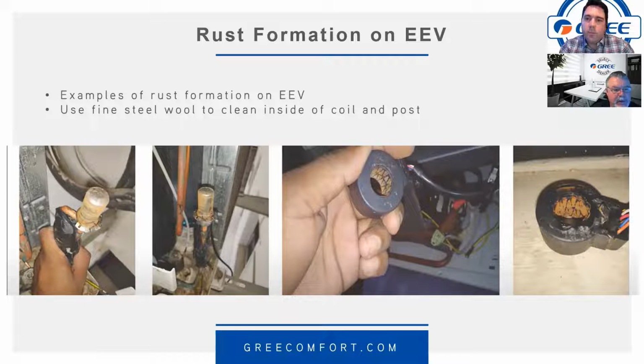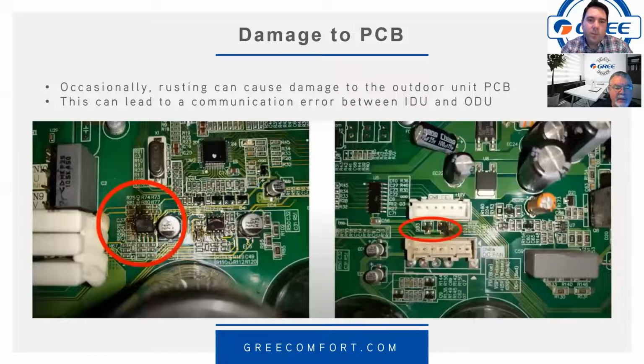Yep, good point. And so here's some other examples, you can see these things are pretty crusty in there. Clean them up. If they're still not functioning properly, you may have to replace them if they've been installed for some time. The other thing that can lead to is damage to the PCB. Occasionally, if that moisture is in there, water and electronics don't mix too well, and you could end up with something like this. So just something to keep in mind, something to check.